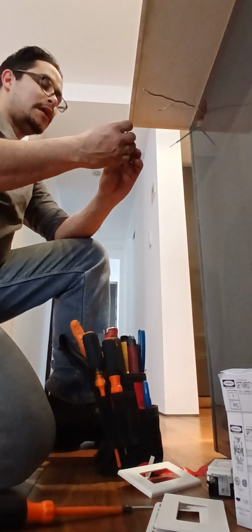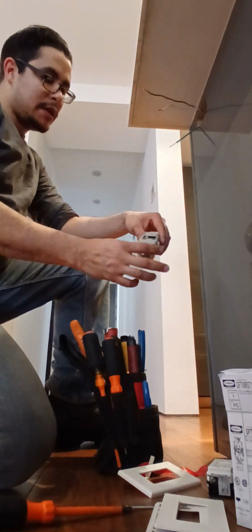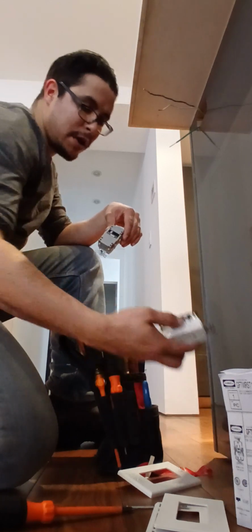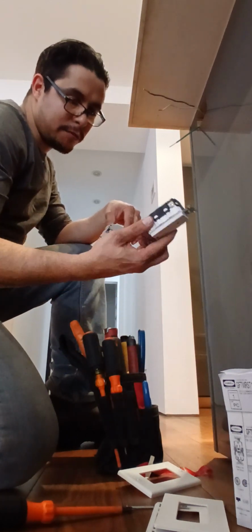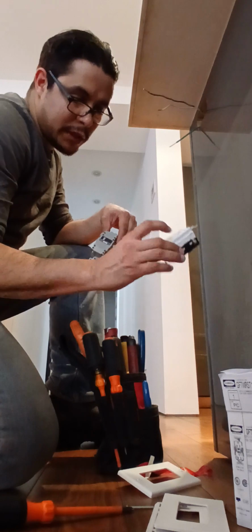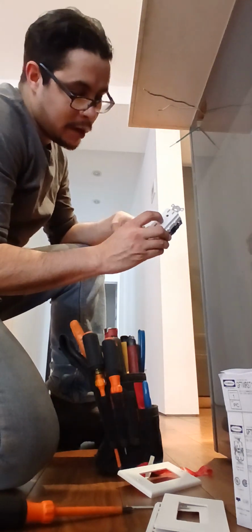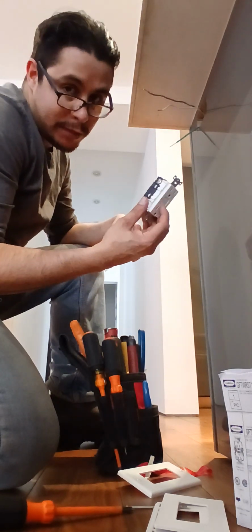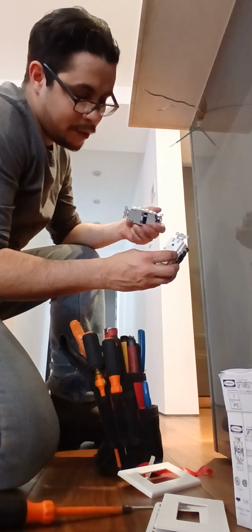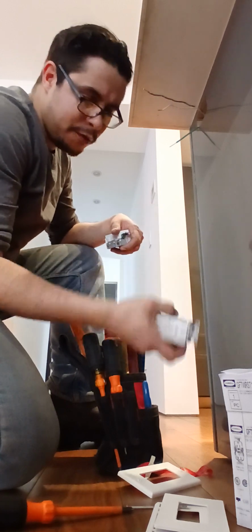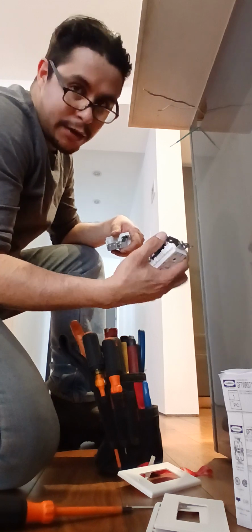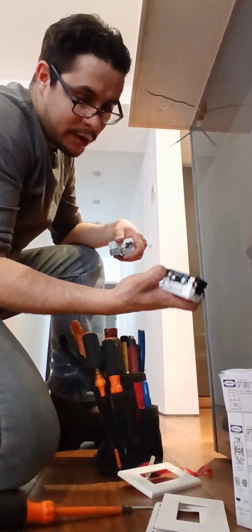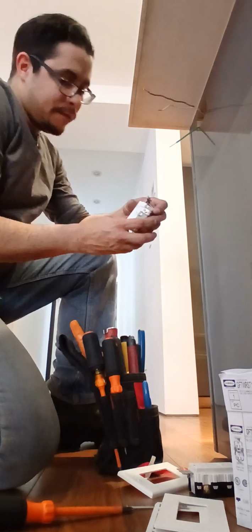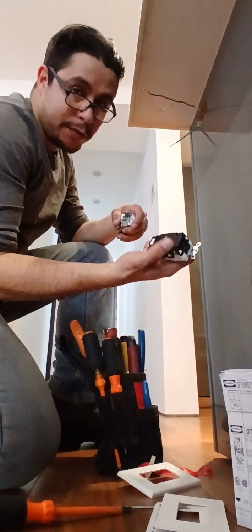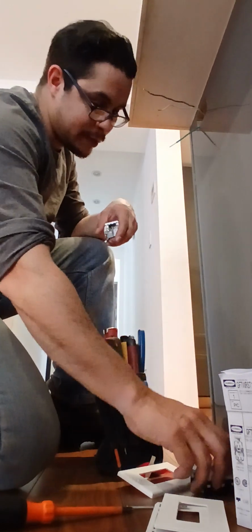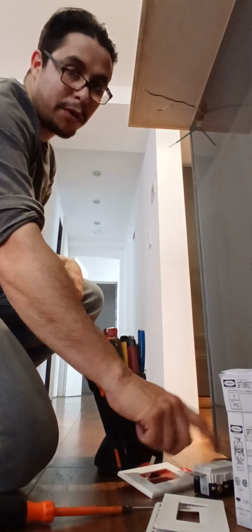With these commercial style ones, normally the residential ones have a sticker. This one doesn't because it's commercial style. The residential ones have a red test button and a black test button, or some are all white, and they have a sticker on the load side telling you not to wire it there. You have to wire it on the line side. If you're protecting other outlets, you wire it at the load side to protect other devices, but this has to be the very first point from the breaker.